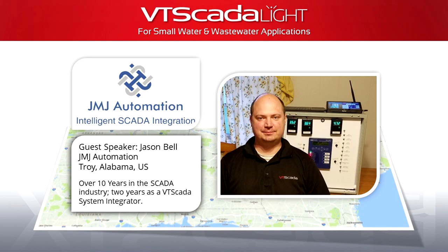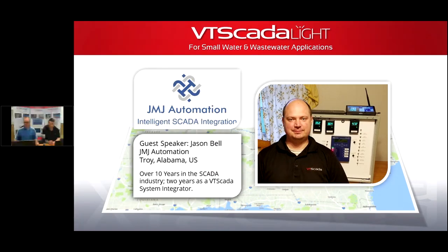So tell us a little bit about what you did for the JAT water system. Sure, for the JAT water system, there are only 400 customers. They only have one well and one tank. And a system that small is not able to actually afford a full-blown SCADA system. So what we were able to do for them, thanks to VTScadaLIGHT, was go in. VTScadaLIGHT, by the way, can run on a $200 Windows 10 computer from Amazon, and it does really well. It's only got 2 gigs of RAM and an Atom processor. And we were able to provide a solution for them that they could actually afford that they wouldn't be able to afford otherwise.